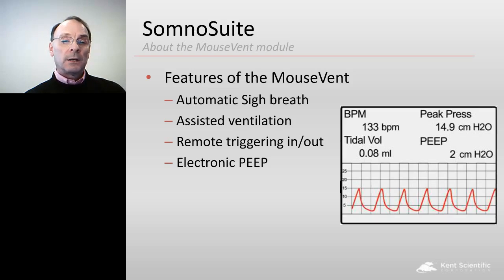The triggering for the assisted ventilation either waits for an animal to breathe, or if it doesn't receive a breath within a certain period of time, which the user can set, it will automatically give a breath to make sure that the animal is not expiring or dying. You can have remote triggering in or out, which is particularly important for imaging, and electronic PEEP.